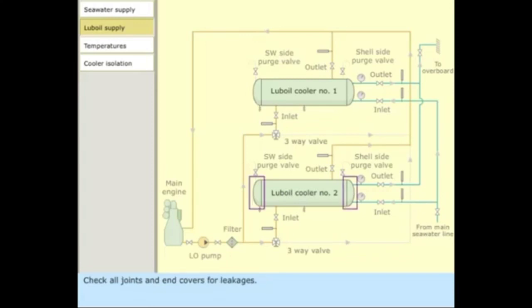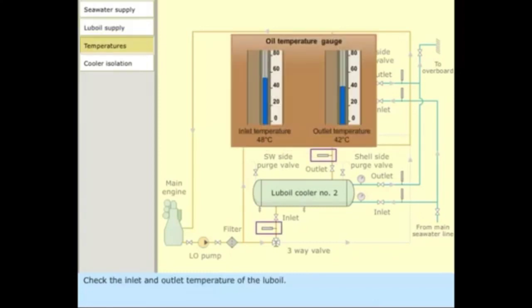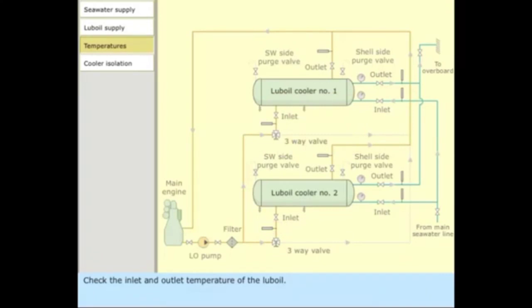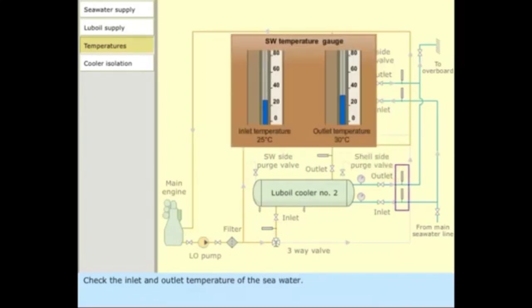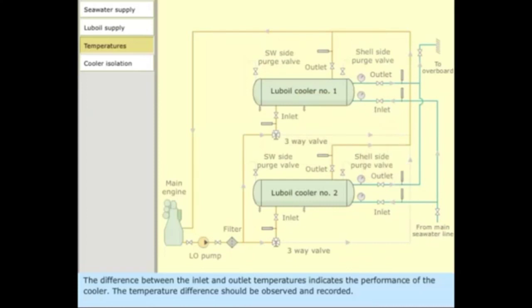Check all joints and end covers for leakages. Check the inlet and outlet temperature of the lube oil. Check the inlet and outlet temperature of the sea water. The difference between the inlet and outlet temperatures indicates the performance of the cooler. The temperature difference should be observed and recorded.